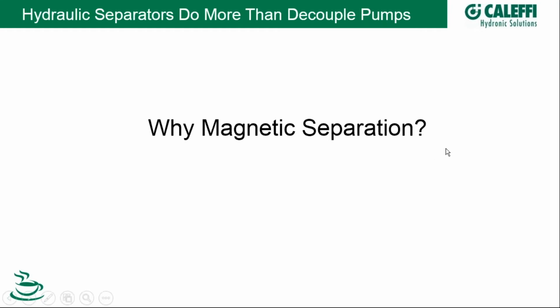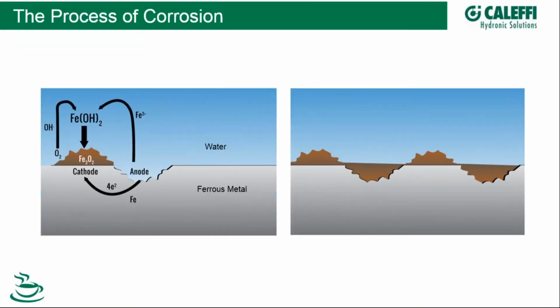So think about any hydronic system. Even if your hydronic system has stainless steel heat exchangers inside of your modulating condensing boilers or your heat pump, and you have all copper piping, and your terminal units are aluminum or copper or both, think about all the other things that could be steel in that. Your pumps, the volutes in your pumps, are typically going to be cast iron. Your expansion tank, on the inside, away from the bladder, is going to be what? Some ferrous metal. You probably can think of others. So there's going to be some ferrous metal that is going to have experienced some corrosion.